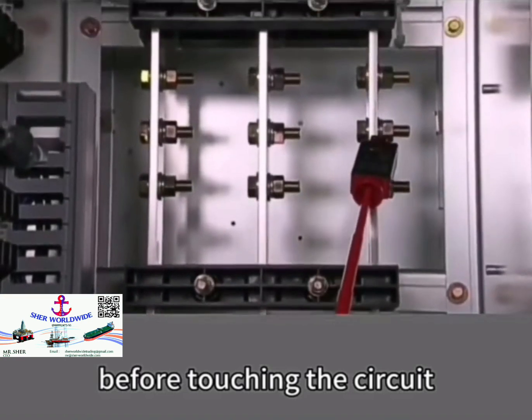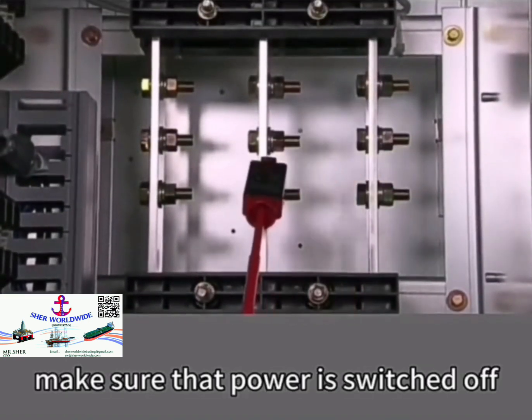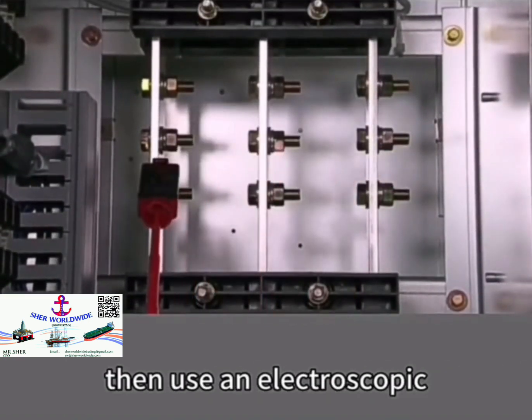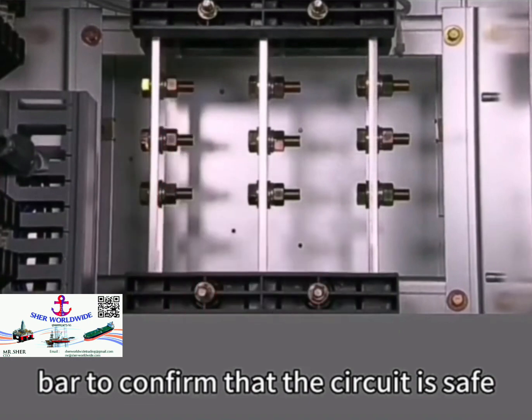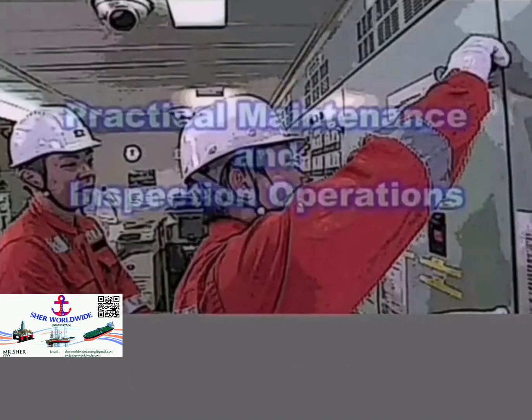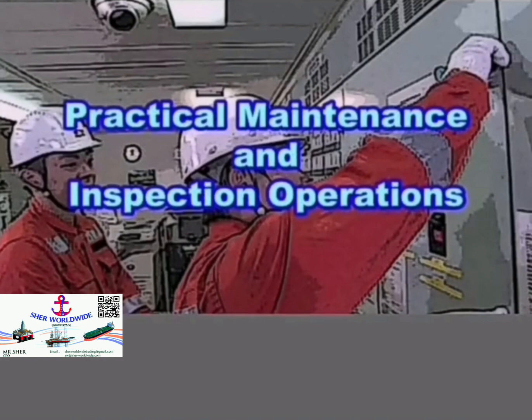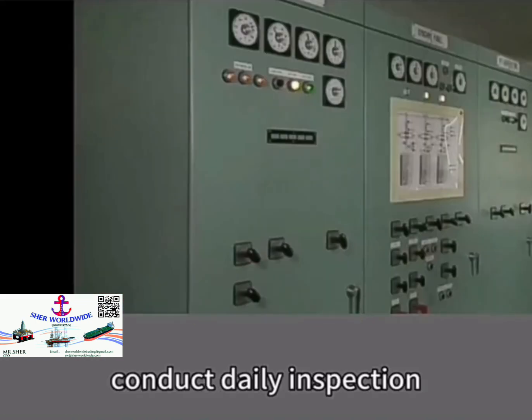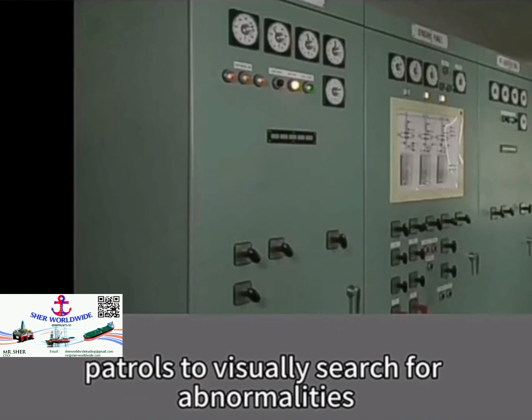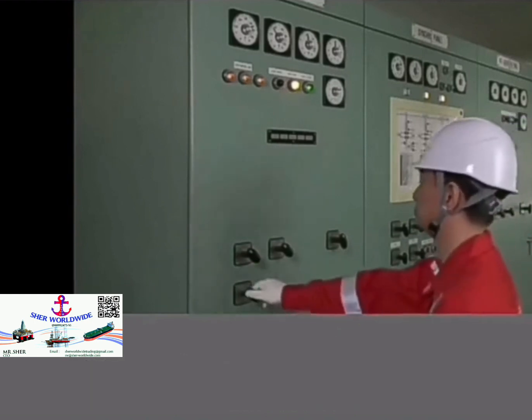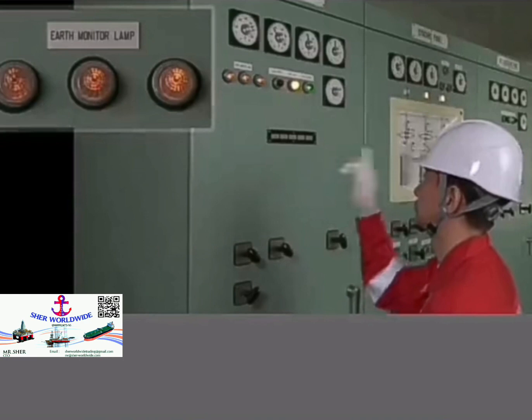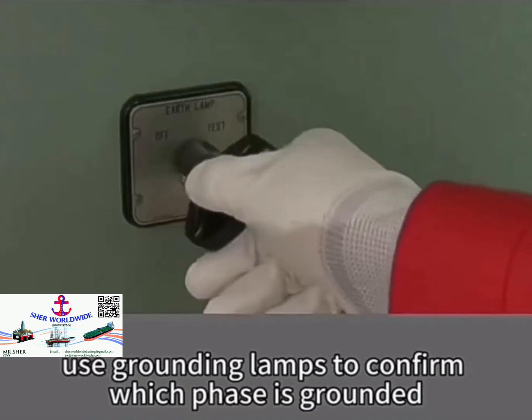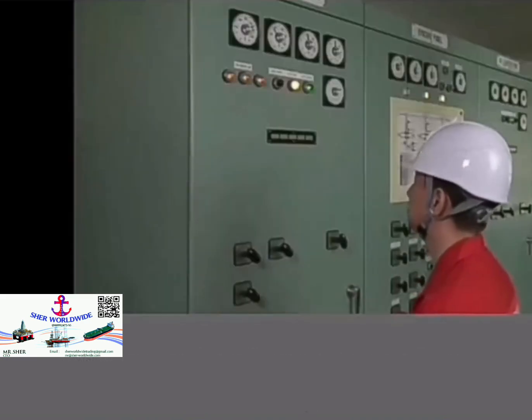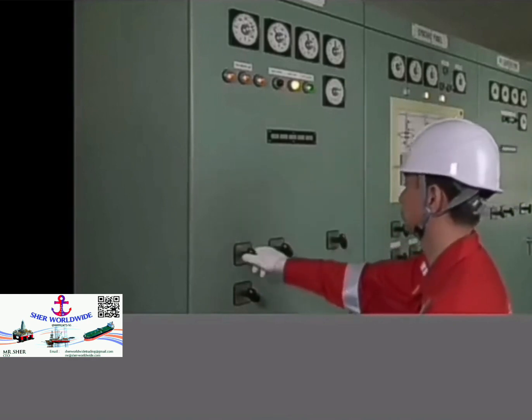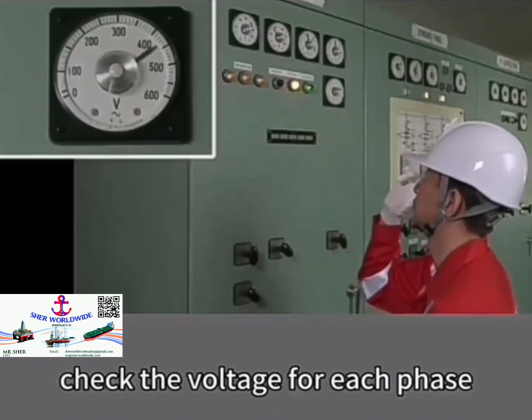Before touching the circuit, make sure that power is switched off. Then use an electroscopic bar to confirm that the circuit is safe. Conduct daily inspection patrols to visually search for abnormalities. Use grounding lamps to confirm which phase is grounded. Check the voltage for each phase.